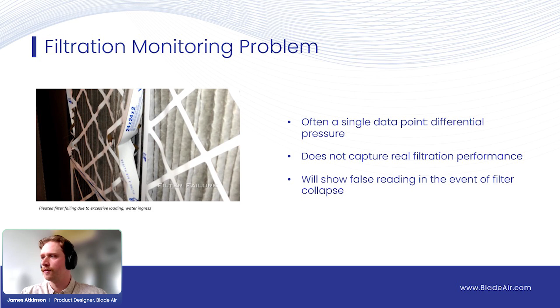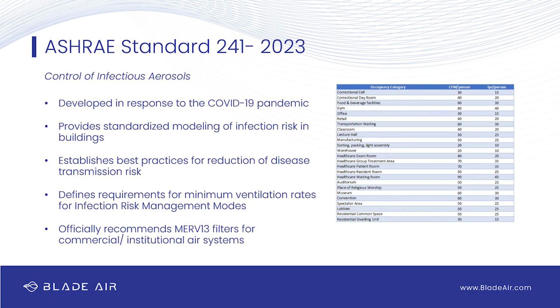But I think recently, especially after the COVID-19 pandemic, we've seen a huge change towards more strenuous filtration. And a lot of that actually comes from the ASHRAE standard 241. So it was released in 2023 after the COVID-19 pandemic. ASHRAE had been releasing some documents with best practices and recommendations throughout the pandemic, but it wasn't codified and really fully released until 2023 because it obviously requires a lot of testing, modeling, that sort of thing. And really what it is a standardized modeling system of infection risk in buildings. It uses the Wells-Riley model to measure risk, but basically it's a CFD simulation to say if there's one person coughing in room A, is it going to make everyone sick in room A or maybe room B, the entire building?